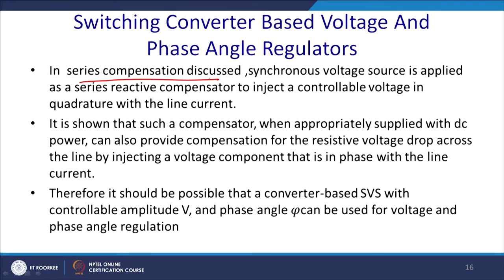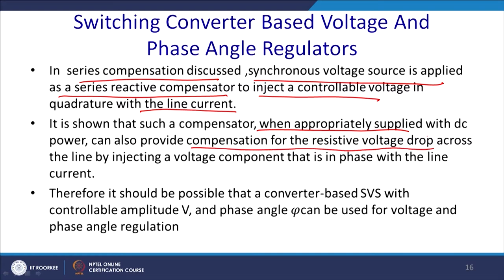So, the switching converter based voltage and phase angle regulator, let us have a comparison between these two. Series compensation discussed: a synchronous voltage source is applied as a series reactive compensator to inject a controllable voltage in quadrature with the current. So, this is the principle of operation. It is shown that such a compensator, when appropriately supplied with a DC source or DC power, can also provide compensation for the resistive drop across the line by injecting the component that is in phase with the current.